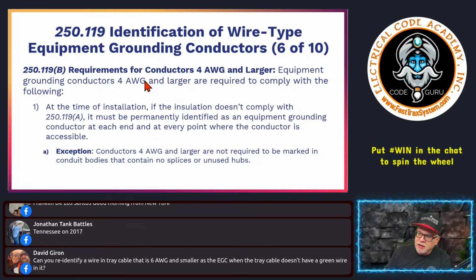250.119(B) says that equipment grounded conductors 4 and larger are required to comply with the following. Number 1, at the time of installation, if the insulation doesn't comply with 250.119(A), meaning it's not green or green with a yellow stripe, it must be permanently identified. And again, this is not specific to any cables or any type of wiring method. This is in general, okay? So it can apply to cables, it can apply to conductors in a raceway, all that type of stuff, okay? It says it must be permanently identified as an equipment grounded conductor at each end and every point where the conductor is accessible.